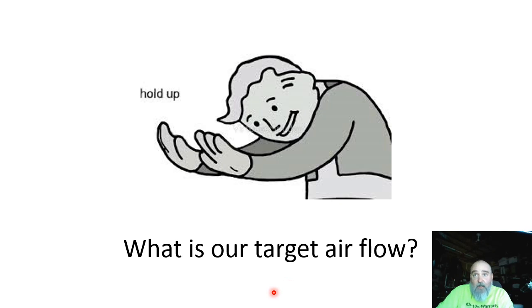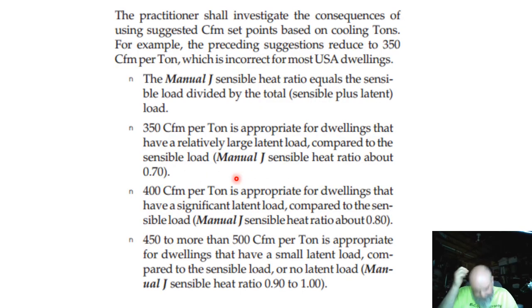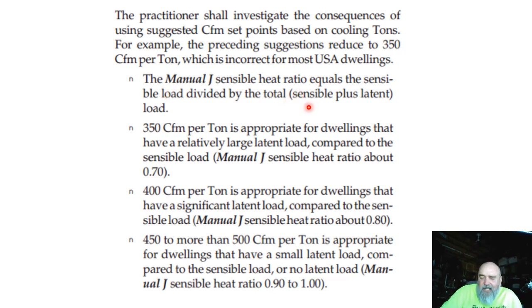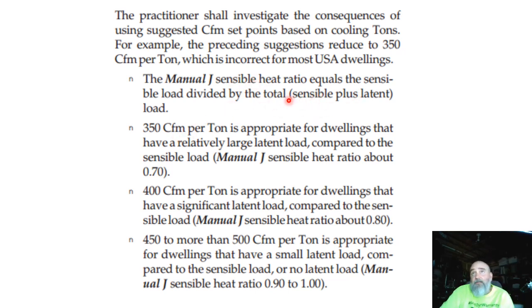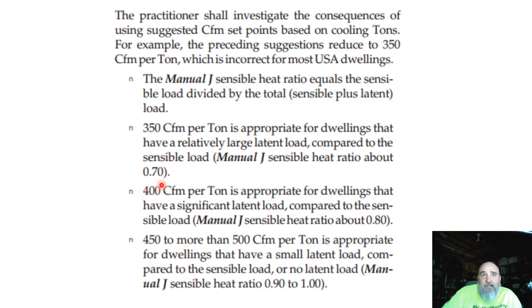This image addresses what our target airflow is supposed to be, and we're going to get guidance from Manual S. Manual J is telling us that our sensible heat ratio is going to dictate what our airflow is supposed to be. Our sensible heat ratio is calculated by taking our sensible BTUs divided by our total BTUs from our load calc. 350 CFM per ton is appropriate when you've got a wet house — a sensible heat ratio of 0.7. Where your house is located doesn't necessarily dictate that number; it's how leaky the house is.